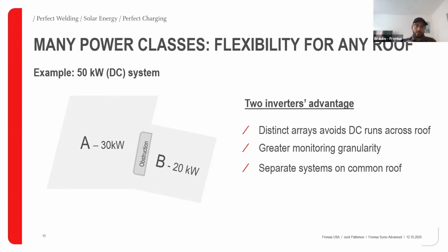Also, if greater granularity of monitoring is desired, having two inverters gives you 4 MPPT channels to monitor instead of 2 or 3 MPP channels. If the building owner wants roof area A to service one tenant's electrical meter and area B to service another's, it's simple with 2 inverters. In fact, the 2 tenants might even have different voltage services. Let's say, in building A, there's the 240 delta, and on B, there's a 208 delta.